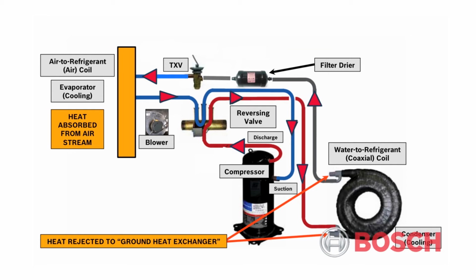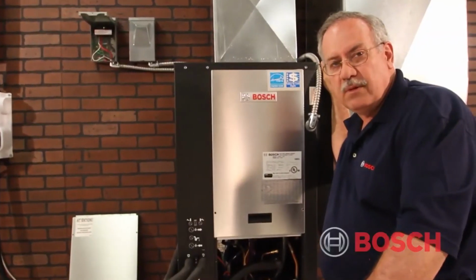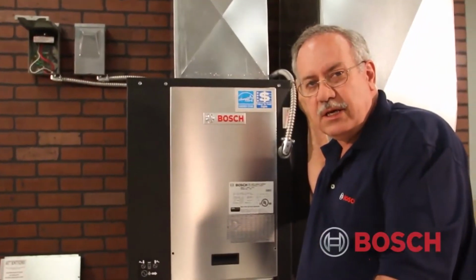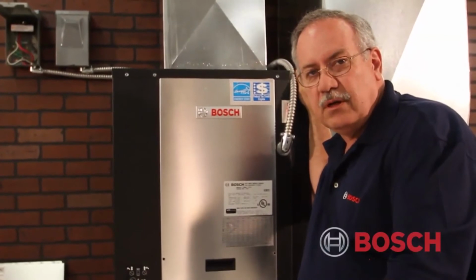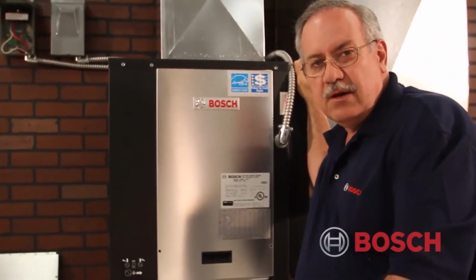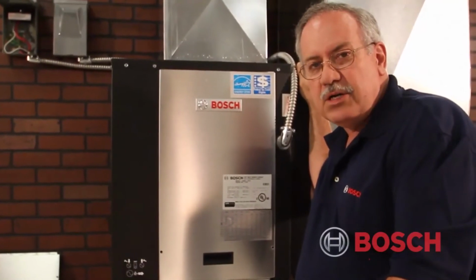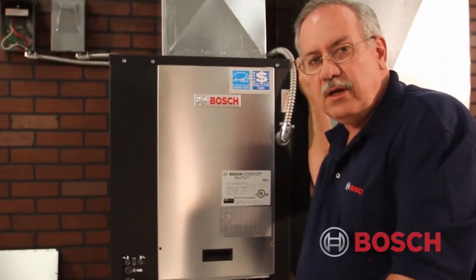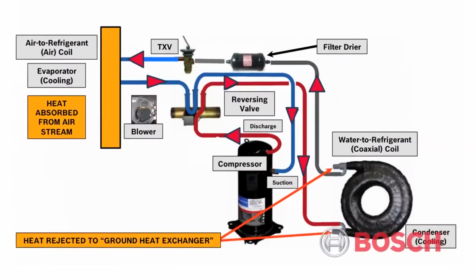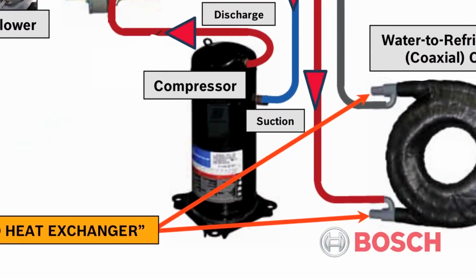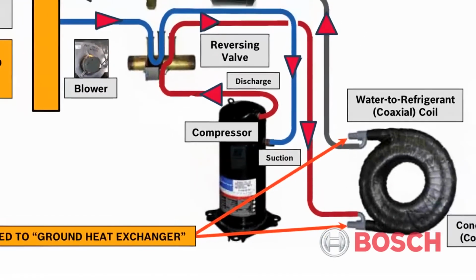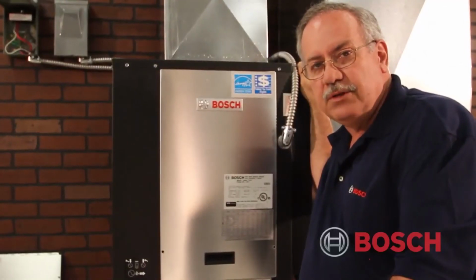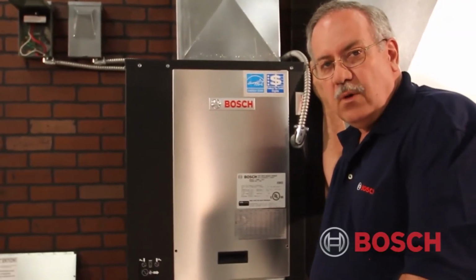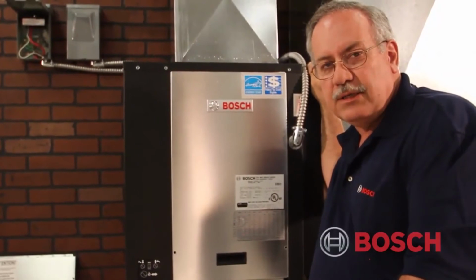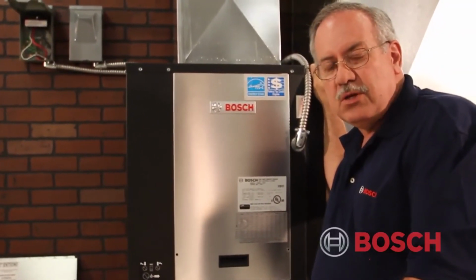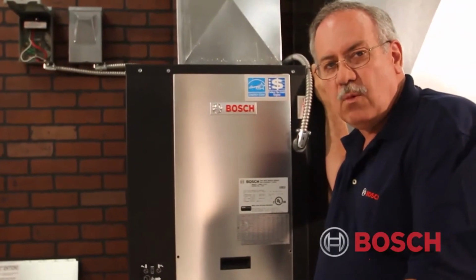Now if I do have to check it in cooling, then I could energize it or change it from one mode to the other in the winter and check it in the heating cycle. In the heating cycle, the refrigerant will approach the operating metering device first instead of the dryer. Additionally, we want to check it in full load. This particular unit has an Ultratech Copeland compressor in it, which is capable of 67% first stage in heating or cooling and 100% in full stage, or Y1 and Y2. We'll always want to check the unit in the water side diagnostics in full load. That means either jumping it out or calling for it and keeping it in Y2 mode.